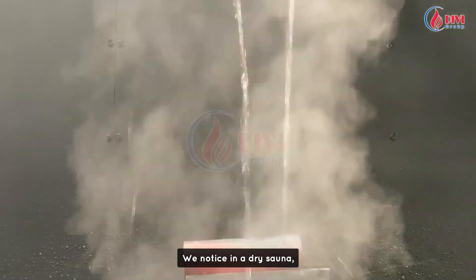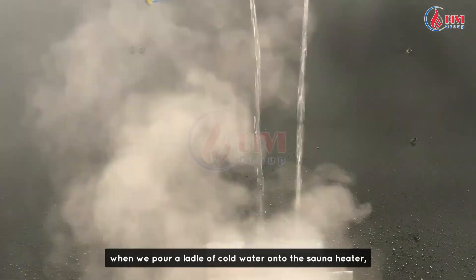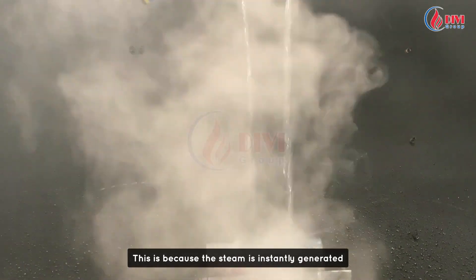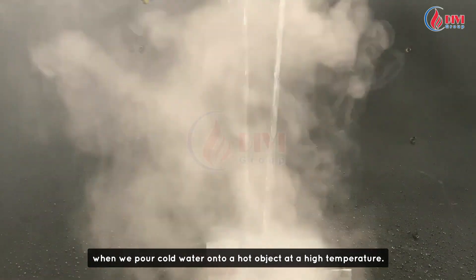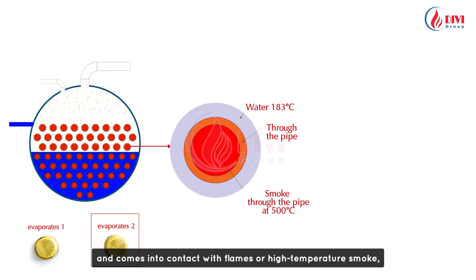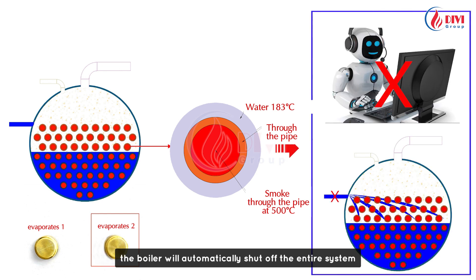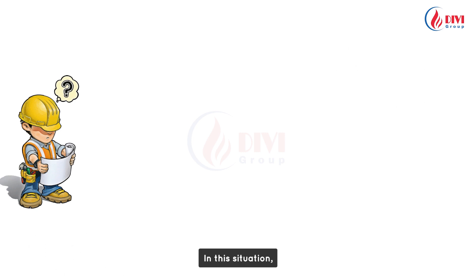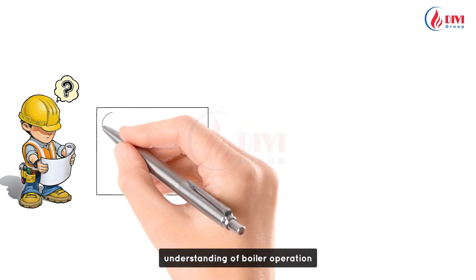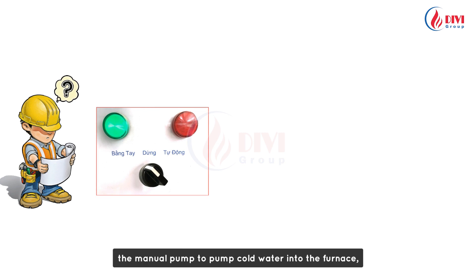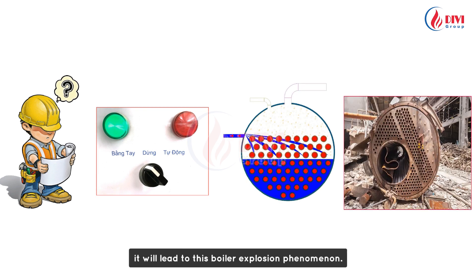Consider a dry sauna: when we pour a ladle of cold water onto the sauna heater, we see a strong burst of hot steam, because steam is instantly generated when cold water contacts a very hot object. Therefore, when the boiler runs out of water for the second time — meaning part of the steel is no longer submerged and contacts flames or high-temperature smoke — the boiler will automatically shut off the entire system and cannot operate in automatic mode, to prevent pumping cold water into the furnace. If the operator lacks knowledge and manually pumps cold water into the furnace, it will lead to a boiler explosion. This is the most common scenario currently.